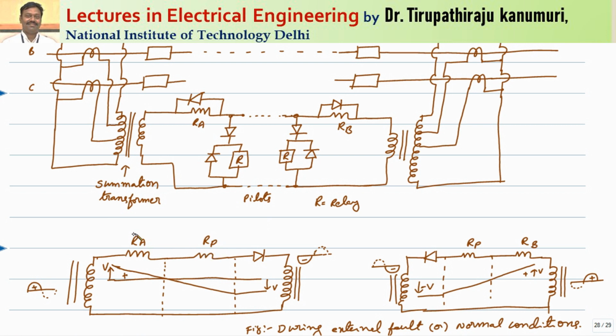I told you already the value of RA is greater than the pilot wire resistance. So voltage will divide among these resistors, because at this point it is V, and at the second side it is minus V. Depending on the resistance values it will divide. As RA is greater than RP, more voltage will drop across RA, because the total difference in voltage is 2V. Out of 2V, more than V is dropped across RA. Or otherwise we can say that at the beginning of RP, that means the beginning of the pilot wire, the voltage will be a little bit negative. It is not even 0, it is a little bit negative.